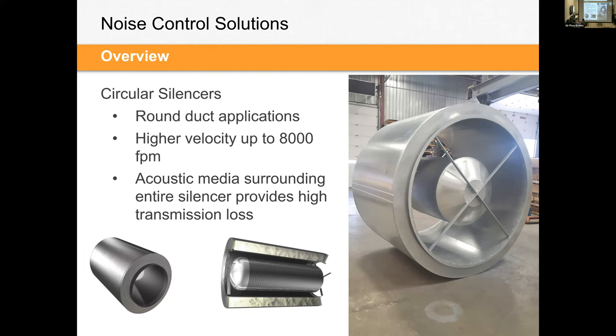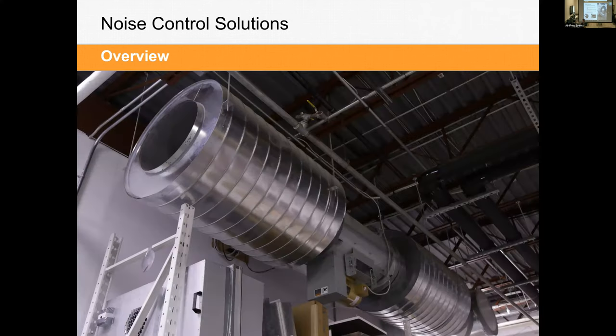We build a lot of circular silencers that get close coupled with fans, whether it's a Cook fan, a Greenheck fan, a Twin City fan, whoever builds the fan. Silencers are often close coupled with centrifugal fans, mixed flow fans and axial fans. There's a lot of science that goes into that, depending on the hub diameter, the flange sizing and so forth, but they can be a great option to attenuate noise directly at a fan. This is a Greenheck QEI fan with an inlet and outlet silencer attached. In this case, we used spiral duct casing to match the rest of the ductwork, concealing it so it's not an obvious noise control device.